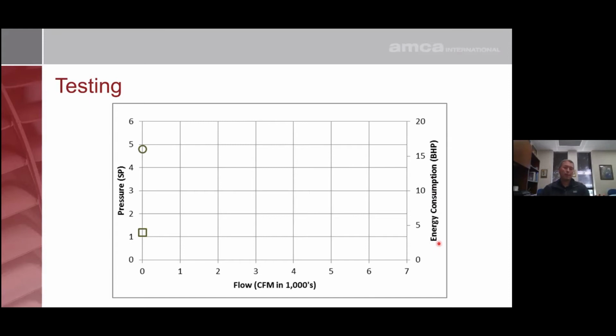And when we test a fan, we typically test first with all the nozzles closed, and we record the work that the fan does. This round dot here is our flow versus pressure dot. And the rectangular dot here is our energy consumption dot. So the fan with the bulkhead nozzles closed off, pressurizing that chamber, is producing about 5 inches of pressure, consuming about 4 brake horsepower at 0 flow.